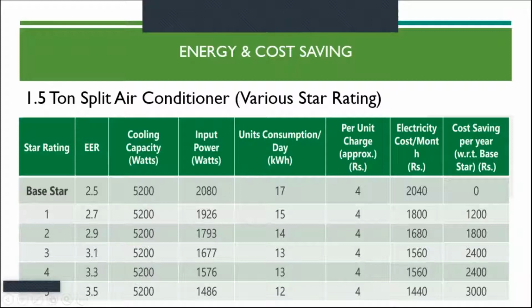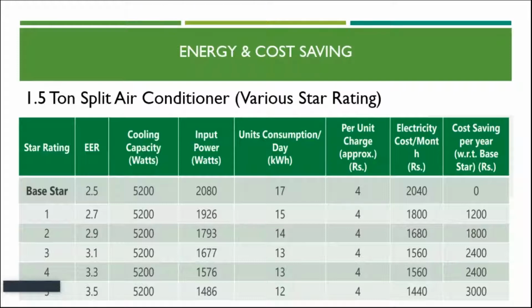So if the running time is lower, we can go for a lower star rating. Like in drawing rooms, we can install a 3-star rated air conditioner. But in a bedroom, where the running time is more, we have to go for 5-star. So this is the procedure of how you can select the star rating of the equipment, and how you can calculate the saving from it.